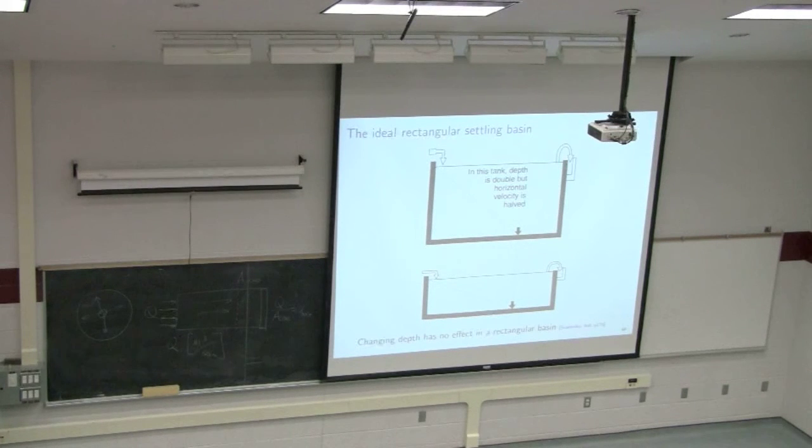So here's why this seems counter-intuitive, that if you double the size of your vessel's depth, it has no effect. When you're doubling that depth, the cross-sectional area through which that Q has to pass, so this flow rate Q, now instead of passing through that depth, is now passing through a larger depth, the velocity in the horizontal direction is halved. So the horizontal velocity is halved, so the particle has got to travel twice the depth, but it's going at half the speed, so it's going to land up at exactly the same point.